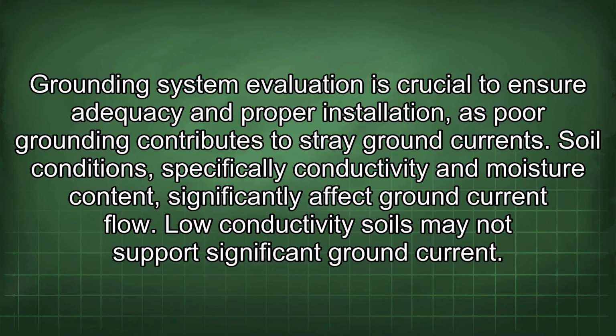Grounding system evaluation is crucial to ensure adequacy and proper installation, as poor grounding contributes to stray ground currents. Soil conditions, specifically conductivity and moisture content, significantly affect ground current flow. Low conductivity soils may not support significant ground current.